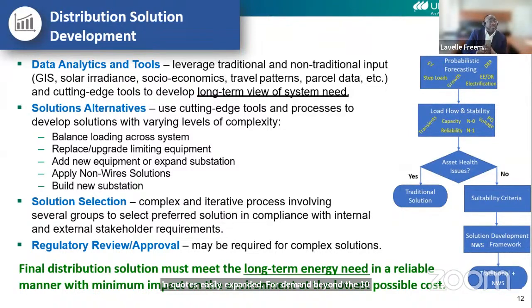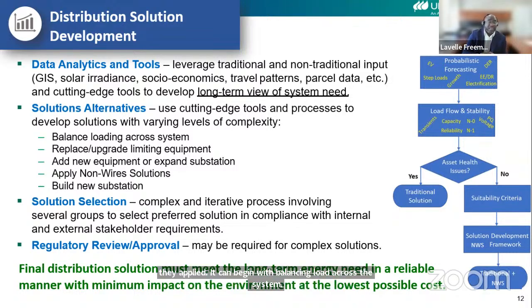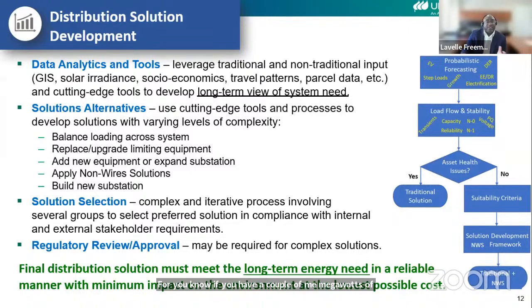The solution alternatives are usually varied in terms of complexity and how they're applied. It can begin with balancing load across the system. If you have a couple of megawatts of thermal capacity violation, maybe by balancing the load you can get a little more out of your system without expensive upgrades. Again, replacing, upgrading, or limiting equipment such as cables and conductors, or maybe upsizing the transformer.